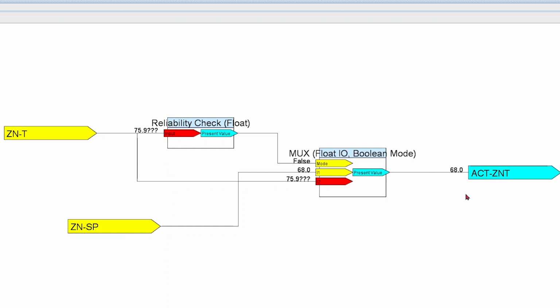So how can you apply this? Let's say that you are controlling a heating valve based on your zone temperature and suddenly you lose the sensor. If your valve PID is 25% open and then you lose the sensor, then your sensor is going to match the actual set point, which means that the PID is going to say, oh okay, the temperature is matching my set point, so I'm going to hold my heating valve at that 25%. So it's a way of holding your valve at its last position when you lose your sensor. Give it a try and let me know if that works for you.